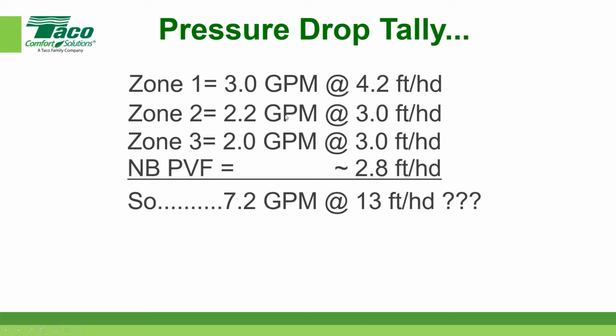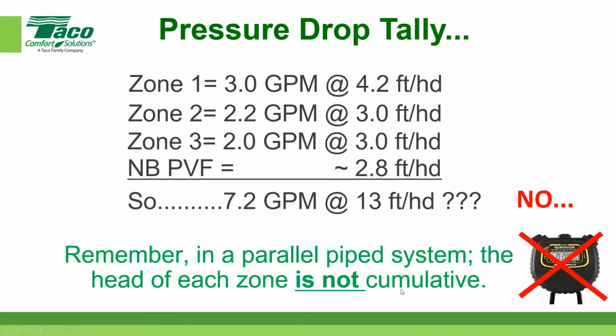Okay, they take this column and they add it together, and they should. But because they're taking this tally and this column and adding it, they do the same thing over here, and they make a mistake. Now, you folks that know this, hold on to it. That's not what you're supposed to do. That leads to pump oversizing, and where we're going with this is you do not, when things are piped in parallel like they would be on a manifold like that, add the head together. It is not cumulative.